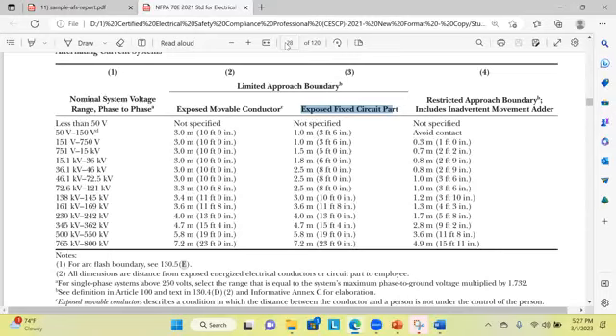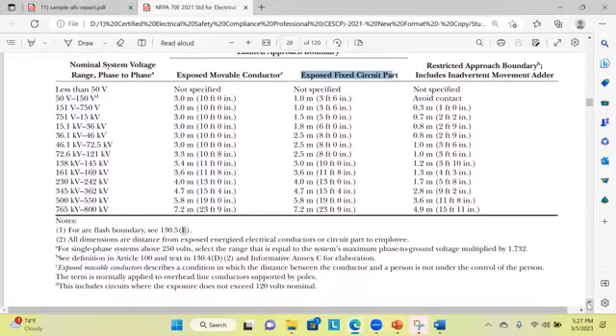Yes, please. Yes, sir. Zishan: The overhead line is considered to be a movable conductor, right? Yes, because there is a sag there, and due to wind the conductors can move a bit. And underground lines we can say are fixed, right? But those are not exposed, so directly there is no shock hazard associated with those. But the busbars, for example the busbars inside the panels, inside your switchgear and switch rooms, will be considered as exposed fixed circuit parts.